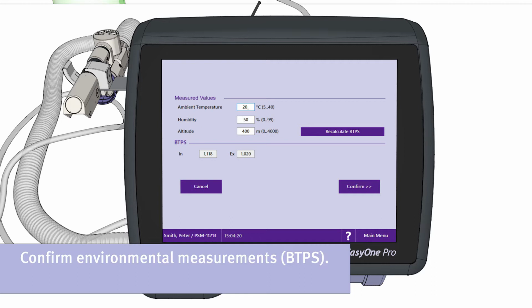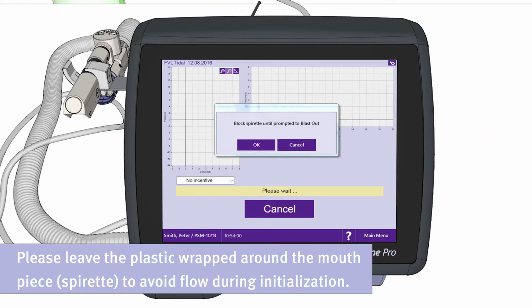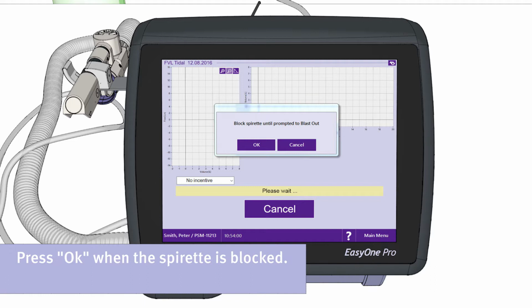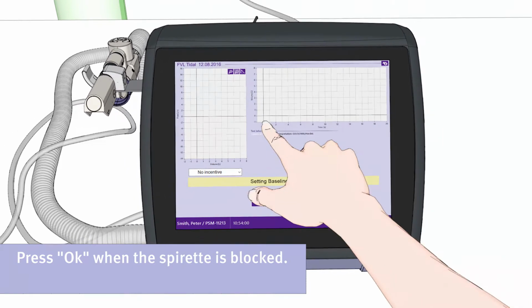Please confirm the environmental measurements BTPS. The temperature, humidity, and altitude are automatically measured by the device. Leave the plastic wrapped around the mouthpiece to avoid flow during initialization. Press the button OK when the spirette is blocked.